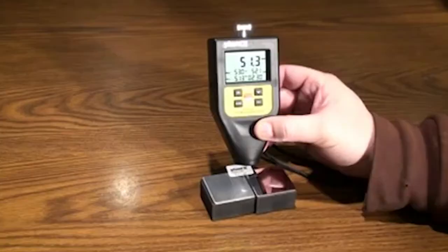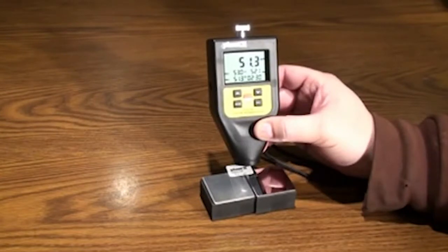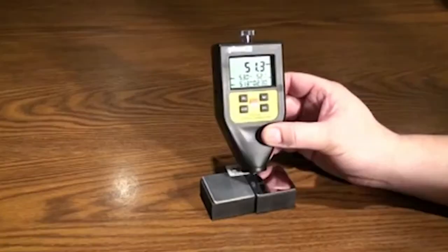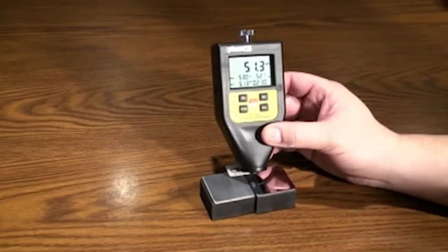This is an instructional video detailing the functions and applications of the Phase II PTG-3700 and 3750 coating thickness gauges. These coating thickness gauges are designed to test non-magnetic coatings on both ferrous and non-ferrous metals. The technology is based on a single multi-purpose probe that combines both eddy current and magnetic induction capabilities in order to auto-detect ferrous or non-ferrous substrates.